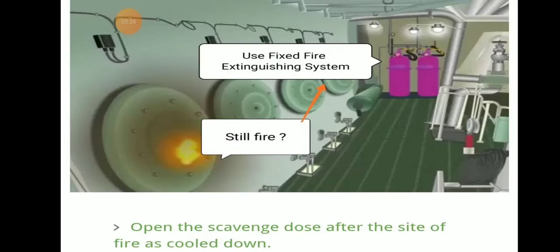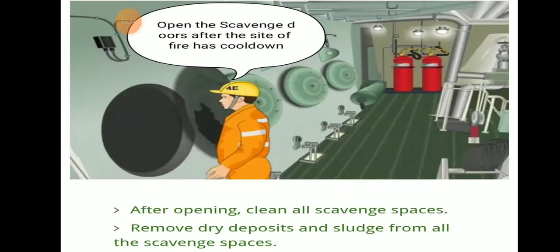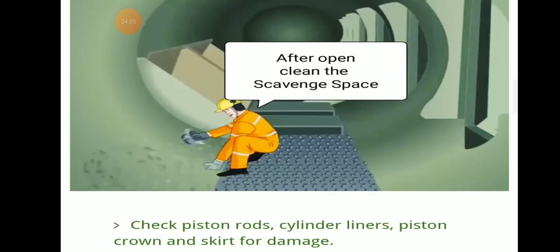If the fire is still burning, we can use a fixed CO2 fire extinguishing medium. After the fire is finished and the scavenge space site has cooled down, we can open the scavenge space doors. Only after the site has cooled down should the scavenge space door be opened.